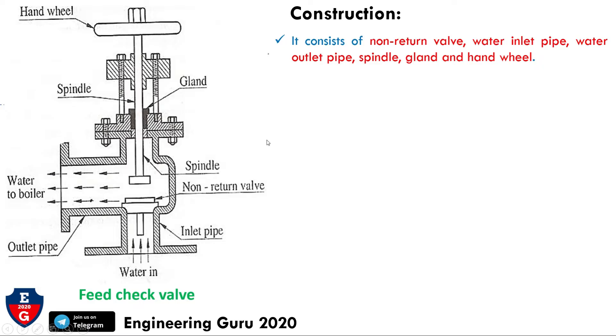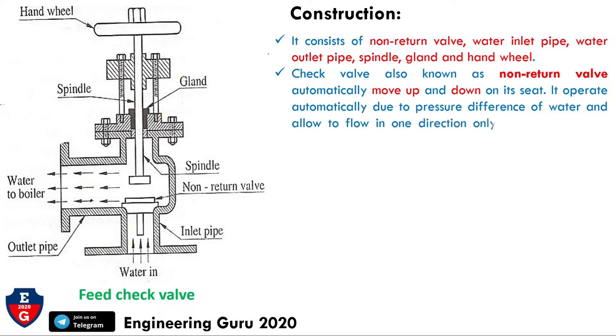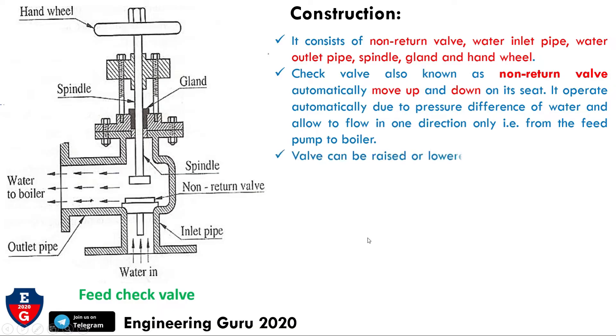The check valve, also known as a non-return valve, automatically moves up and down on its seat. It operates automatically due to pressure difference of water and allows flow in one direction only — that is, from the feed pump to the boiler. This valve is operated due to pressure difference; the valve can be raised or lowered on the gun metal seat with the help of the spindle and hand wheel.